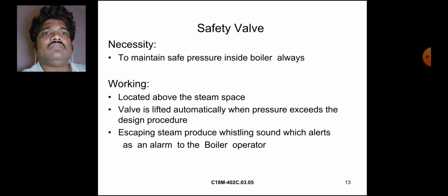The safety valve is necessary to maintain safe pressure inside the boiler always. It is located above the steam space. The valve is lifted automatically when pressure exceeds the design pressure. Escaping steam produces a whistling sound which alerts as an alarm to the boiler operator.